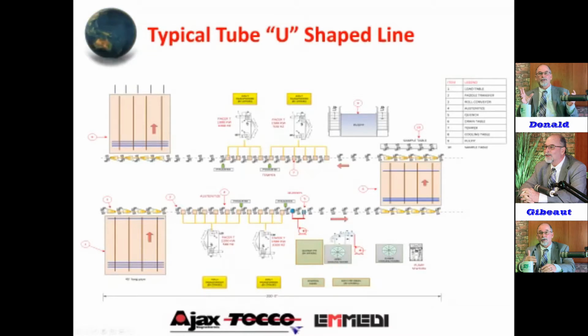You see the quench pit, open tower down here. We do closed towers there as well. Closed cooling system for the more high purity water, because as this hot pipe comes out here it's quenched out, but all the way through this austenitize, it's getting hotter and hotter. So you got to water cool the rolls. Same thing all the way through this temper and all the way out, you've got to water cool your rolls. All that's put on this closed tower here.